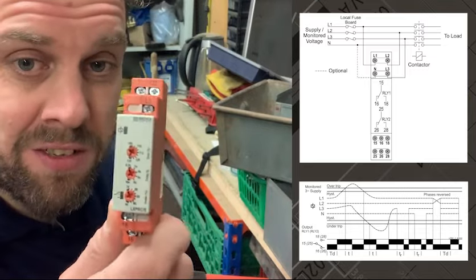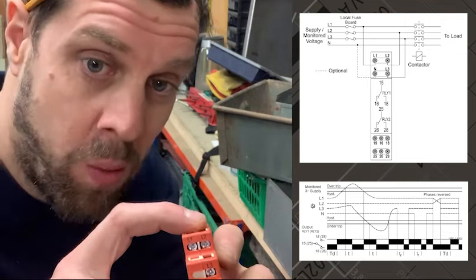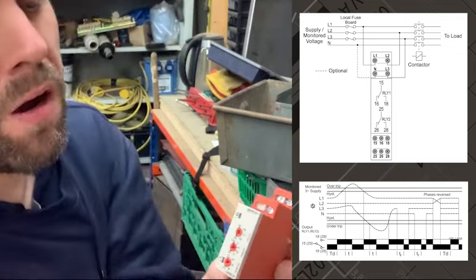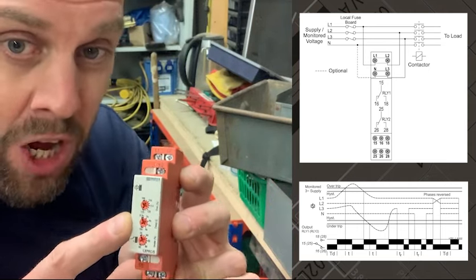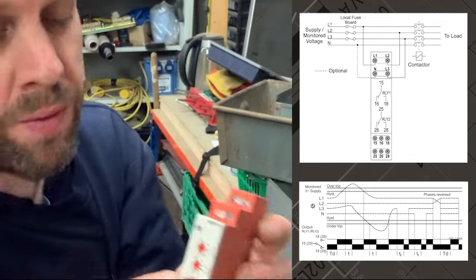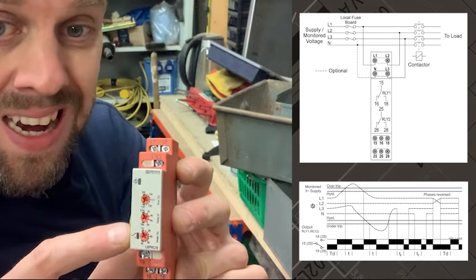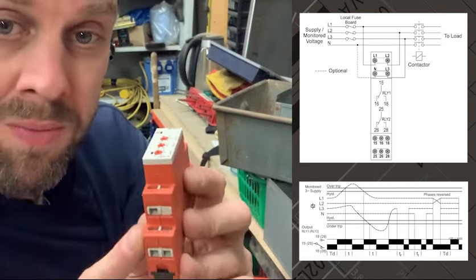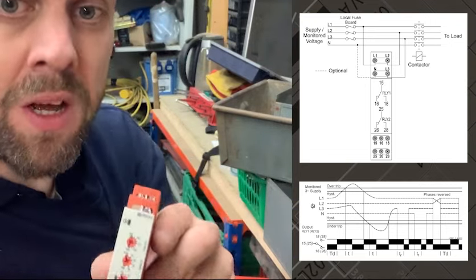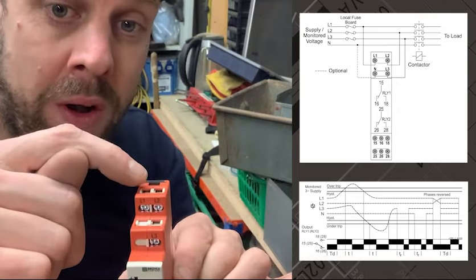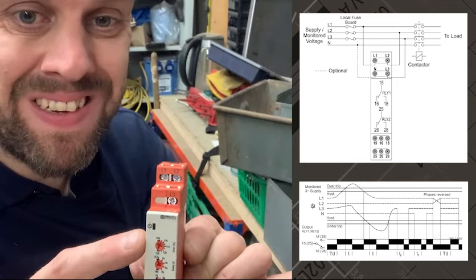This is a very certain type of relay, this is called a voltage monitoring relay. On the top it's got room for L1, L2, and L3. On the front you've got the maximum permissible over-percentage of voltage, the time before it trips, and the maximum permissible under-voltage. You've got a little light to say the contact is closed, the relay is working, and a little light to say that it's powered up. On the bottom you've got a relay - normally open, normally closed, and a common.